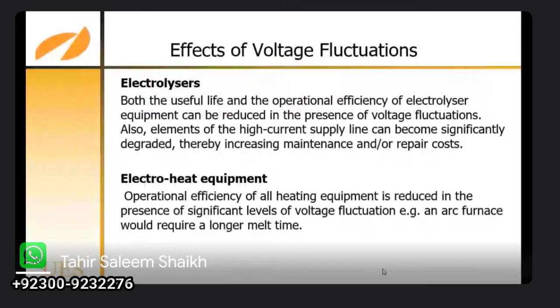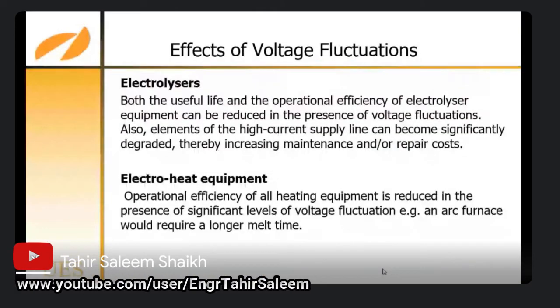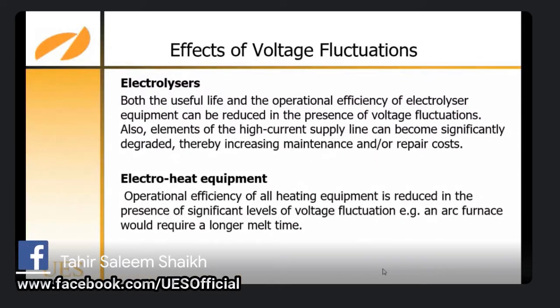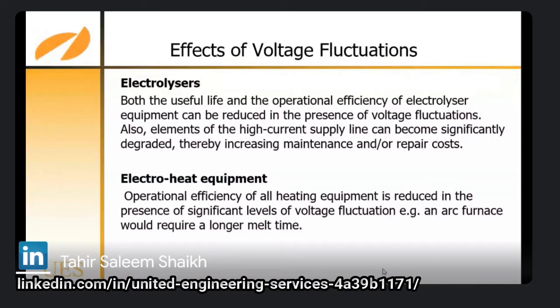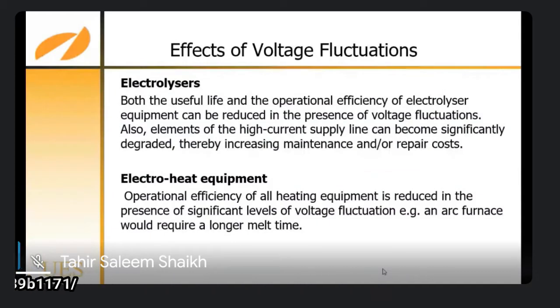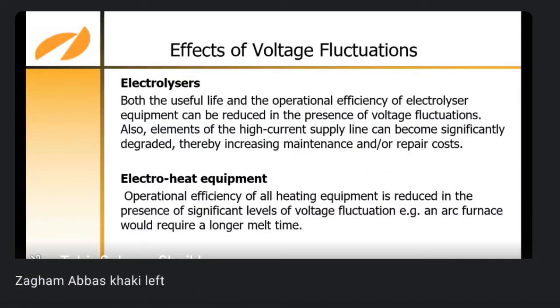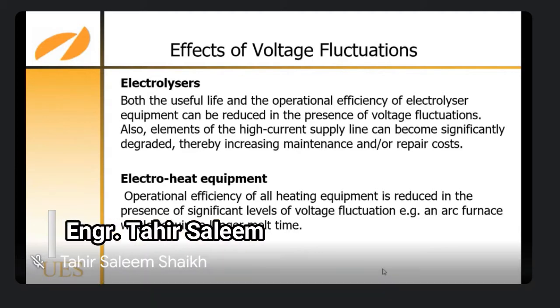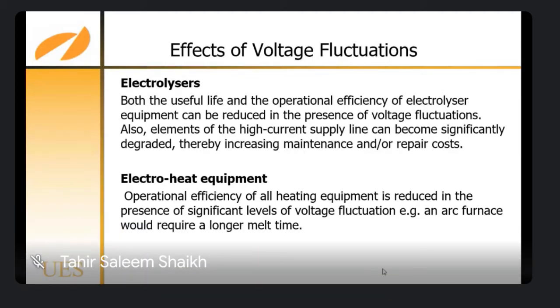Electrolysers. Both the useful life and the operating efficiency of the electrolyzer equipment can be reduced in the presence of voltage fluctuation. Also, elements of the high current supply line can become significantly degraded, thereby increasing maintenance and repair costs. Electro heating equipment. Operational efficiency of all heating equipment is reduced in the presence of a significant level of voltage fluctuation. For example, an arc furnace would require a longer melting time.